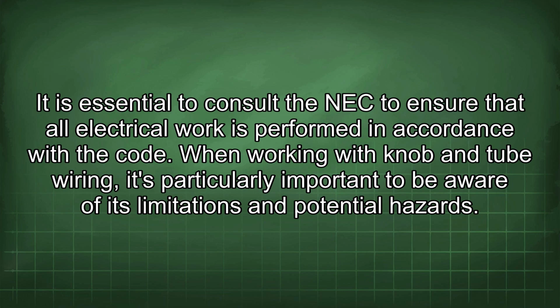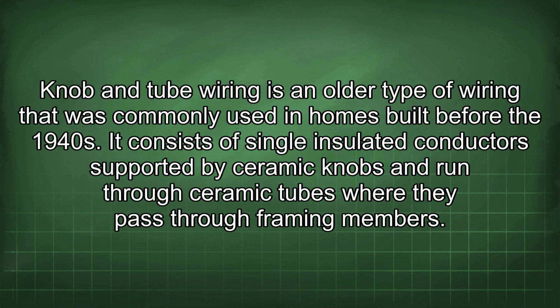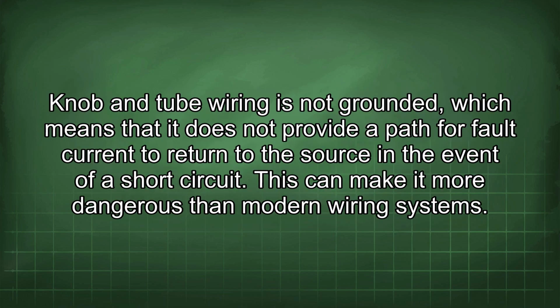When working with knob and tube wiring, it's particularly important to be aware of its limitations and potential hazards. Knob and tube wiring is an older type of wiring that was commonly used in homes built before the 1940s. It consists of single insulated conductors supported by ceramic knobs and run through ceramic tubes where they pass through framing members. Knob and tube wiring is not grounded, which means that it does not provide a path for fault current to return to the source in the event of a short circuit. This can make it more dangerous than modern wiring systems.